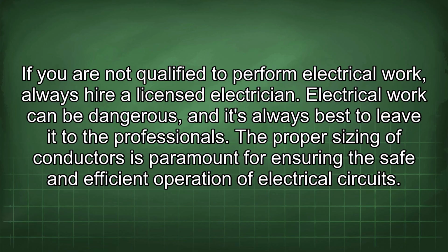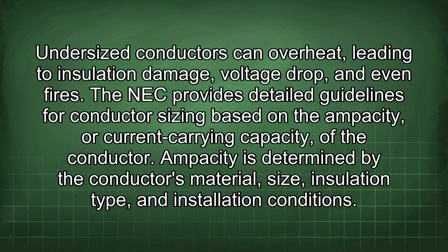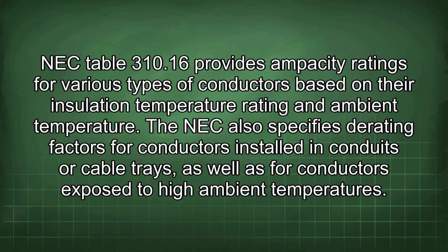The proper sizing of conductors is paramount for ensuring the safe and efficient operation of electrical circuits. Undersized conductors can overheat, leading to insulation damage, voltage drop, and even fires. The NEC provides detailed guidelines for conductor sizing based on the ampacity, or current carrying capacity, of the conductor. Ampacity is determined by the conductor's material, size, insulation type, and installation conditions. NEC Table 310.16 provides ampacity ratings for various types of conductors based on their insulation temperature rating and ambient temperature.